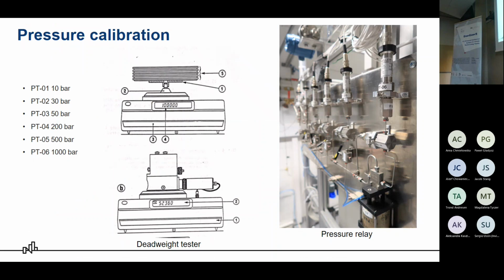Also, we have to calibrate the pressure sensors. So the HVCP facility has 6 sensors from 10 to 1000 bar. And we have to calibrate them, we have to compare them to a deadweight tester. So it is a device where you place plates with very low mass.